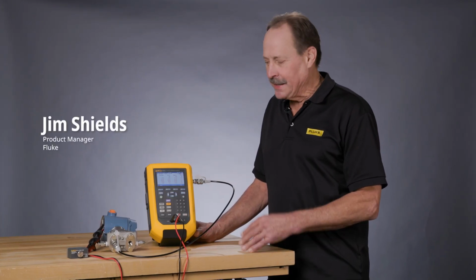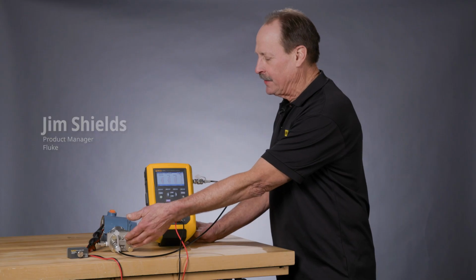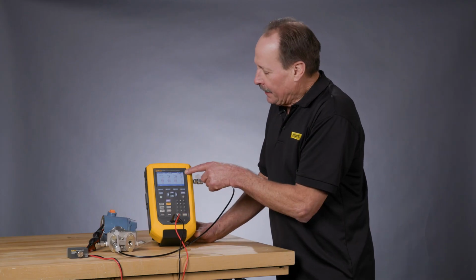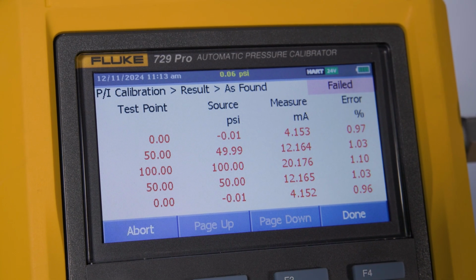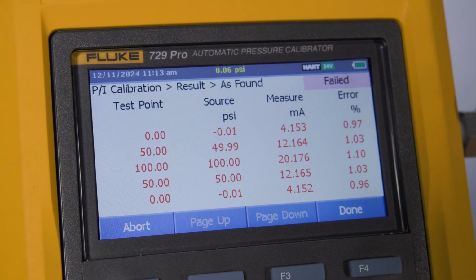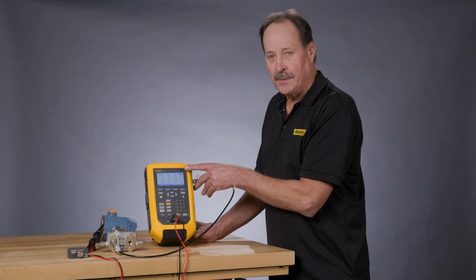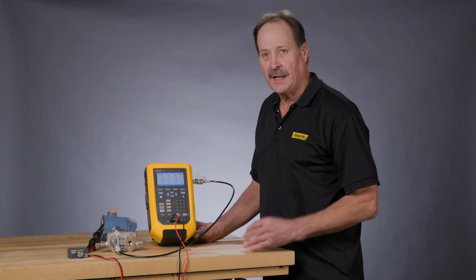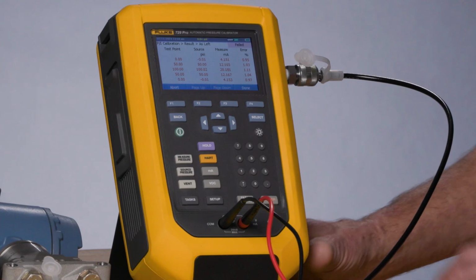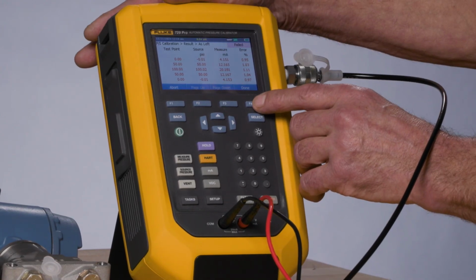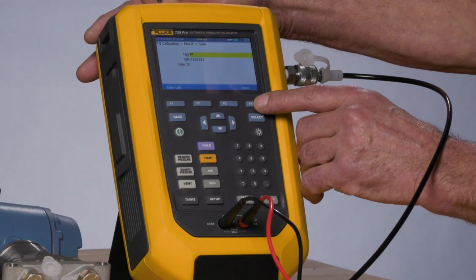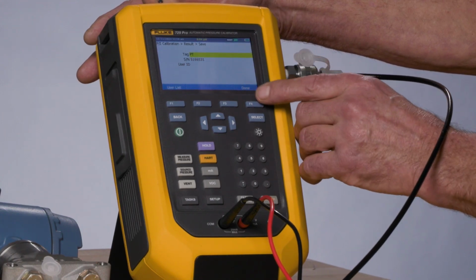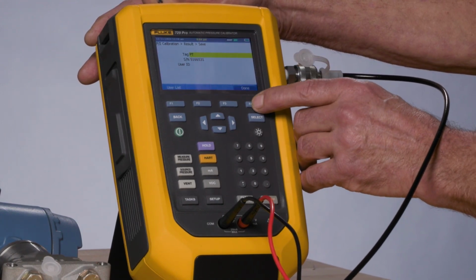We have performed a calibration test on this Rosemount 3051 transmitter, and the as-found test failed. So now we need to do the adjustment using the HART capabilities of the 729 to adjust this transmitter within specification and then run the as-left test. To perform this adjustment, we would select Done from the as-found screen, and we would see the tag and the serial number and the ID information. Done.